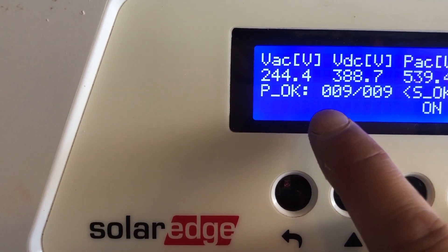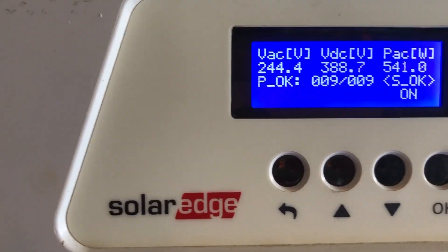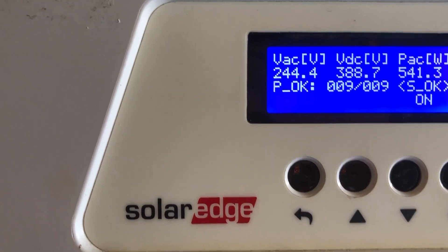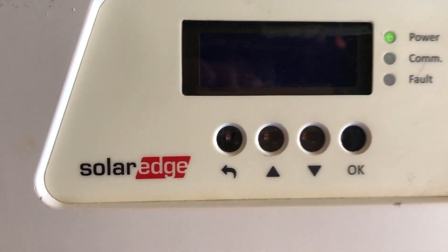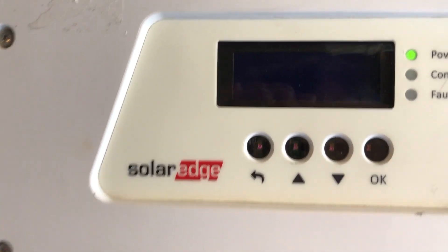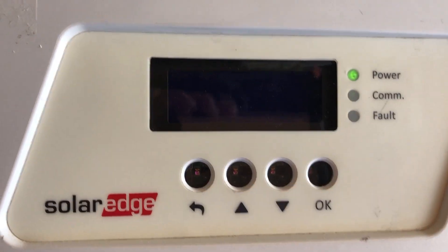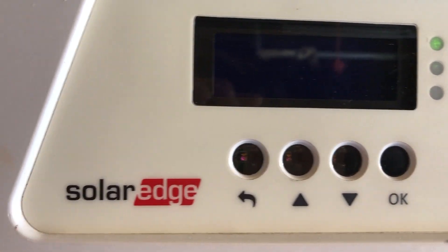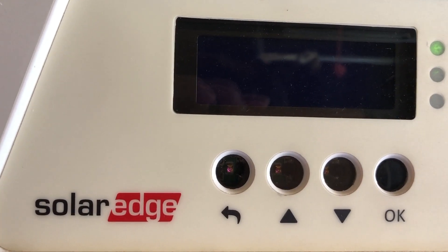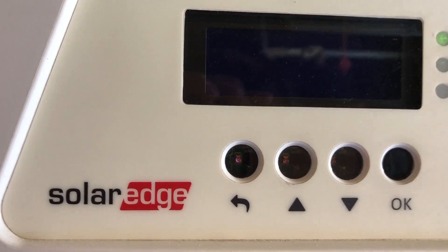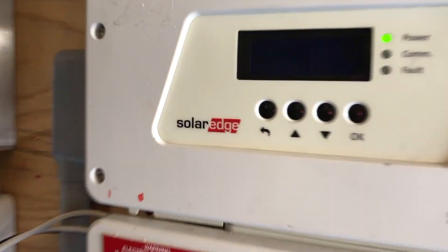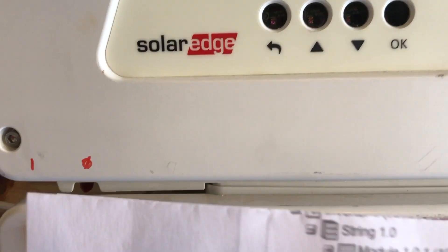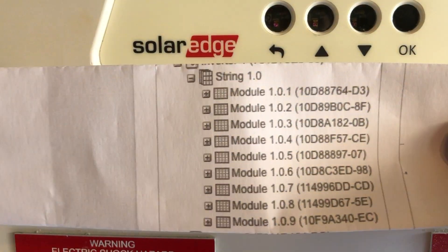This video will show you how to identify which one is actually faulty. First you have to get a list of all the optimizers that are supposed to be available, along with their serial numbers. The easiest way to do that is by using the monitoring system — go to solaredge.com and go to monitoring.